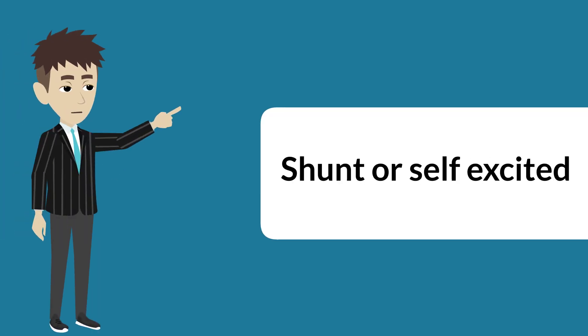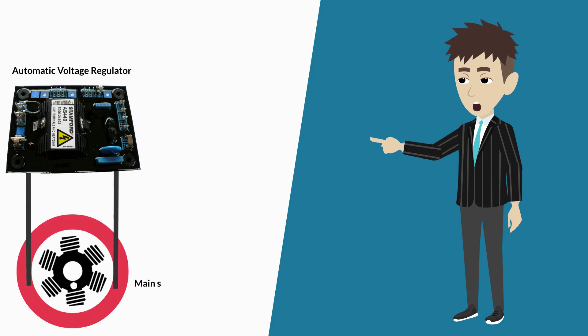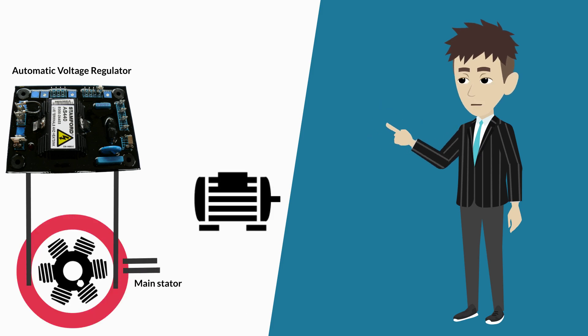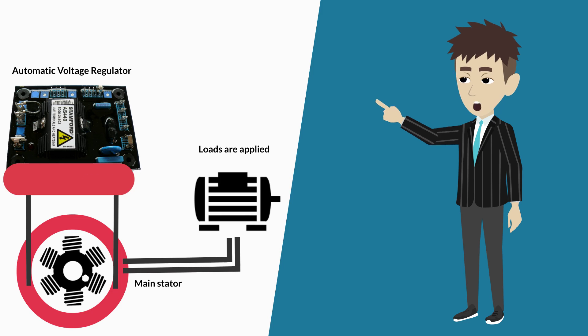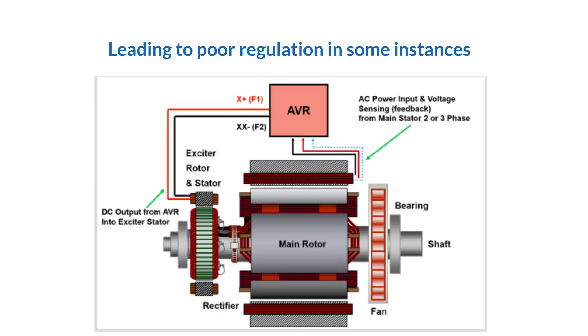In shunt or self-excited, the automatic voltage regulator is powered from the main stator terminals in the alternator, so when high loads are applied, the AVR power supply is also disrupted, leading to poor regulation in some instances.